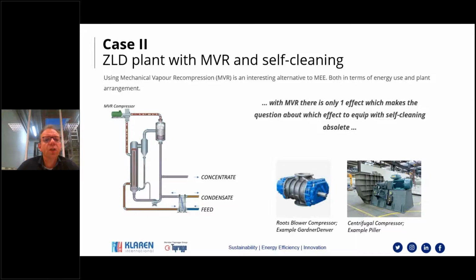You use a compressor to increase the pressure, thereby increasing the temperature, and thereby you can use the vapor as your heating medium on the shell side of the heat exchanger. And at this shell side of the heat exchanger, which you see here on the left, you will condense all the vapor, meaning that you will recover all this latent heat that you have first put in. And the only energy really that you require is this energy of the blower. The required energy of the blower will depend on the compressor ratio that you choose. But more about that in the next slides.